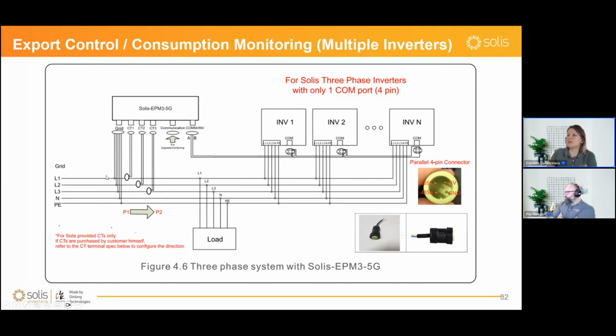What I want to mention is that it's very important to have, for the grid port, the L1, L2, L3 connections. It's very important to have CT1, CT2, and CT3 installed on the same phases, meaning that you have to make sure that the sequence of the phases is actually correct, because otherwise, if you have L1 installed on L2 and L2 on L3, you're going to have a completely different sequence, and the EPM will measure wrong the power values for each phase due to the wrong phase rotation.